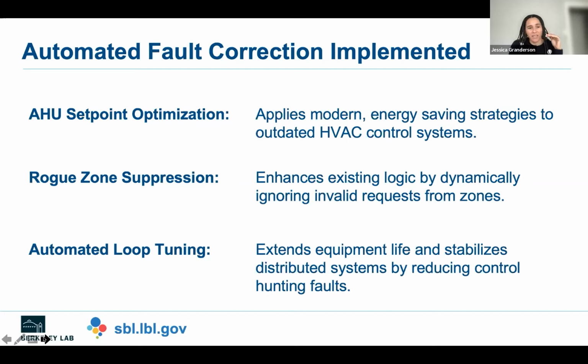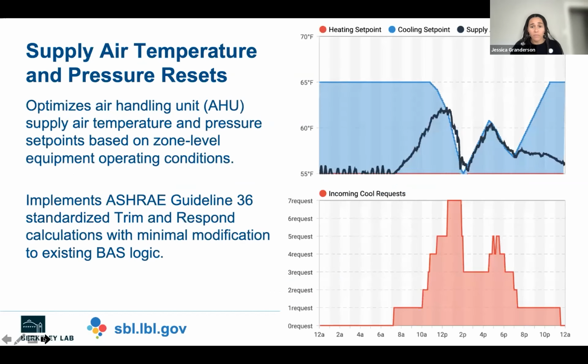The set point optimization and rogue zone suppression was allowing us to apply the best in class sequences of operation, and also enhance the existing logic of the building automation system. In the loop tuning, there are implications there for equipment life and stabilizing the controls across different systems and reducing those hunting faults. So I'll start with the reset strategies.